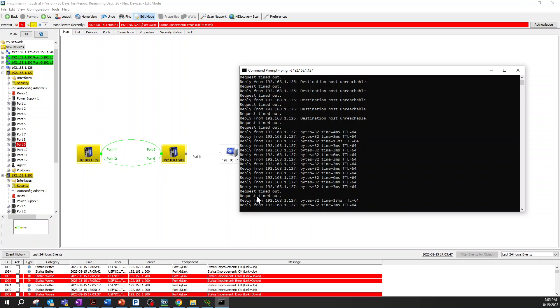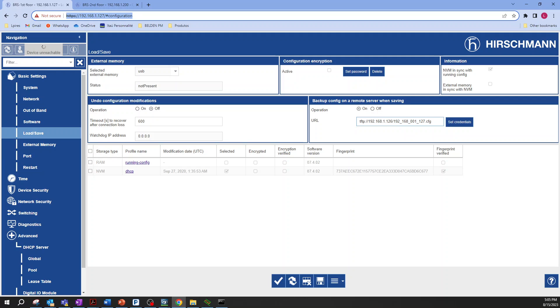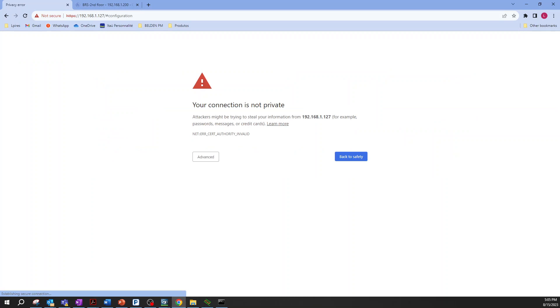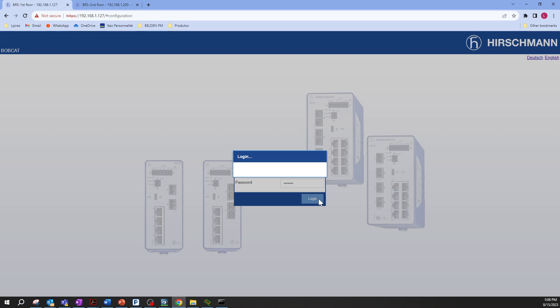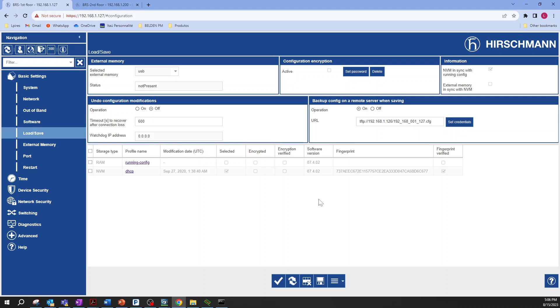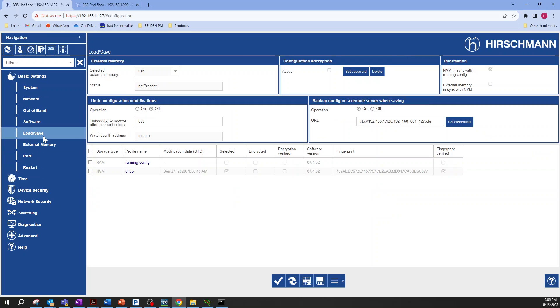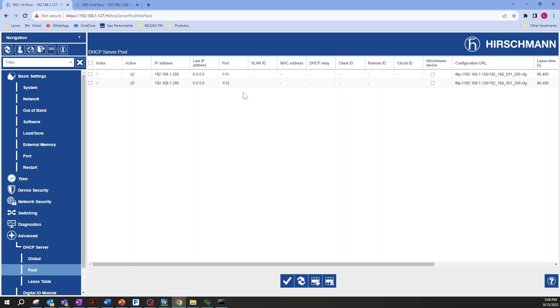It's back and let's take a look on the device configuration. Let's refresh to make sure. Let's access back this device. You see the configuration is back on the address 127. Let's take a look inside. And then you can see the system name, this name I put. And then you can see also the load save configuration is on, the backup config option. Under advanced DHCP server, global is also on. Everything is as per the previous configuration.